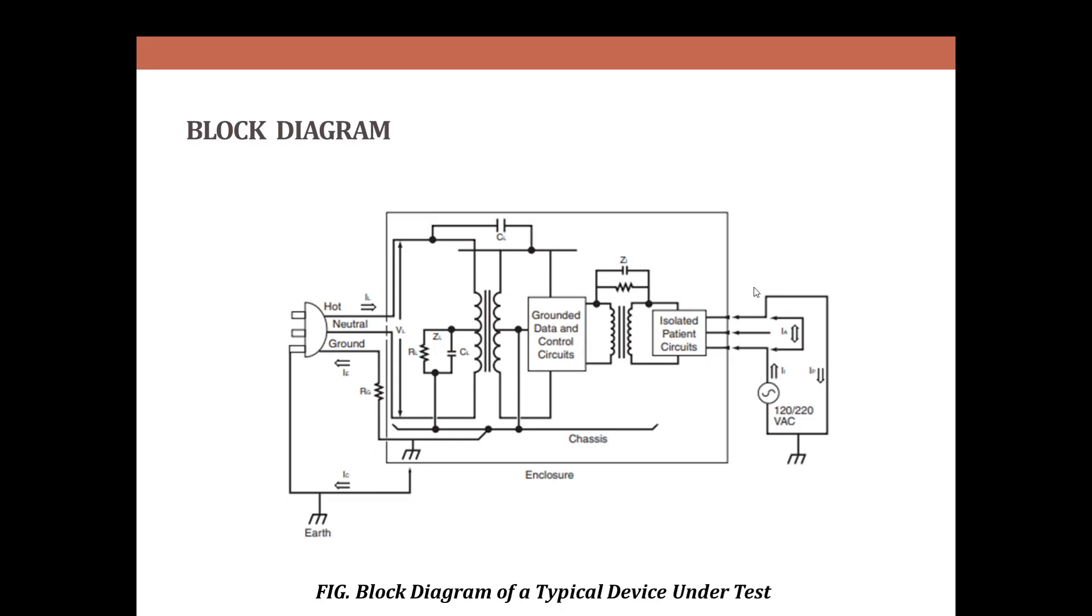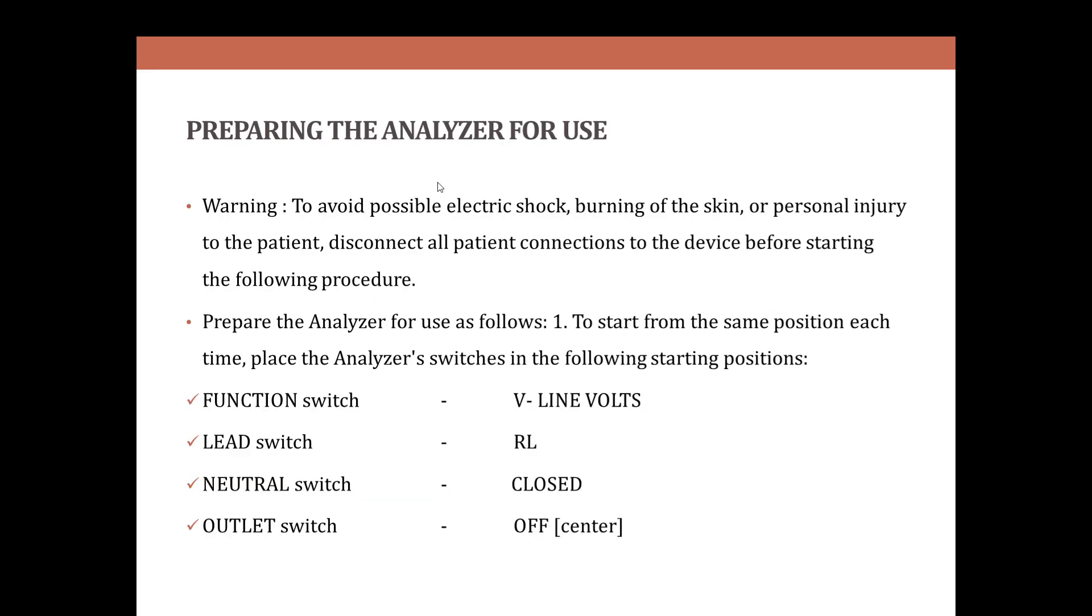Preparing the analyzer for use: The warning is to avoid possible electric shock and burning of skin or personal injury to the patient. Before starting the test, we should disconnect all patient connections so that we can avoid these injuries.